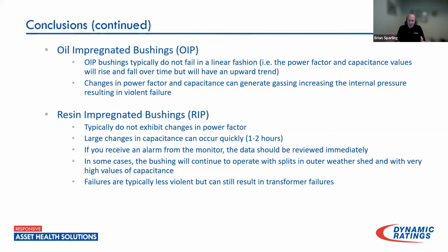That utility's process was: the alarm came in, they had subject matter experts look at the data and determine, right, we need an outage. They would phone their friends in operations and, depending on the trend and the rate of change of the data, arrange for an outage the following day. So now they can plan to get the right crew, the right equipment, and the right bushing up for replacement, and have all that prepared to take the outage, to test the bushing, confirm that it is bad, and replace the bushing.